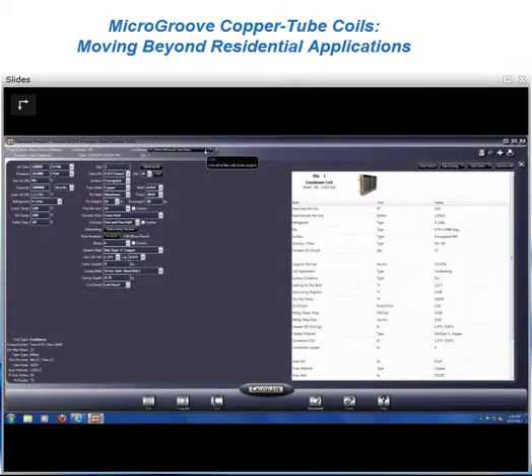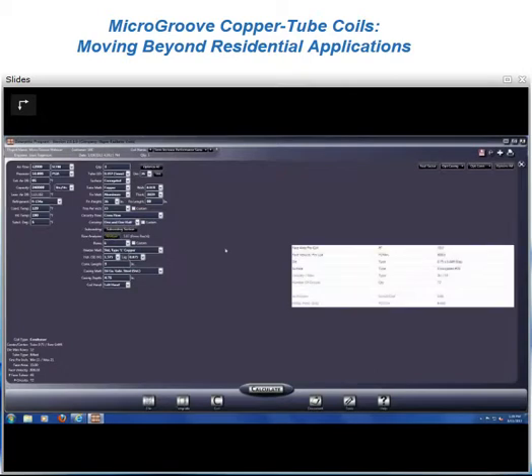The last design option may be, what if I don't want to change my footprint, or I don't need to change the footprint? Let's keep the footprint the same of the coil and increase the performance. So we'll go back to our 5mm coil. And we'll just do some selections here to get us back to the coil at 36-inch fin height. Excuse me, we lost a little bit of data there. And our 60-inch fin length. And this particular coil is going to be 1.5 circuited. So let's just analyze that real quickly. It tells me I need 5.97 rows.